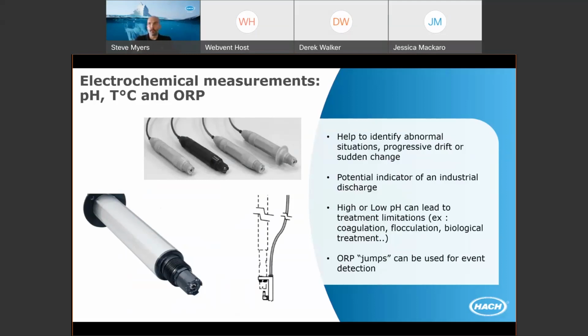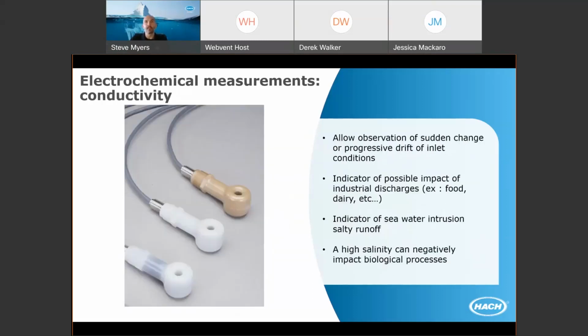For the ones we're showing here, these are Hach differential electrode measurements. They use a 3-electrode setup instead of the traditional 2 electrodes used in conventional pH sensors. This improves robustness, accuracy over time, reliability, and reduces downtime and maintenance. That said, they will require some regular maintenance such as cleaning, and air blast systems can be added to automate some of that, or at least lengthen the time between manual cleanings.